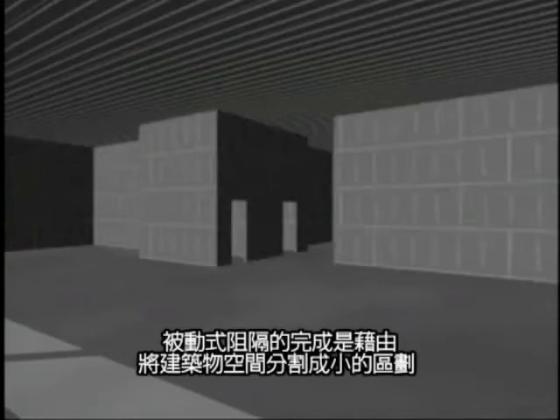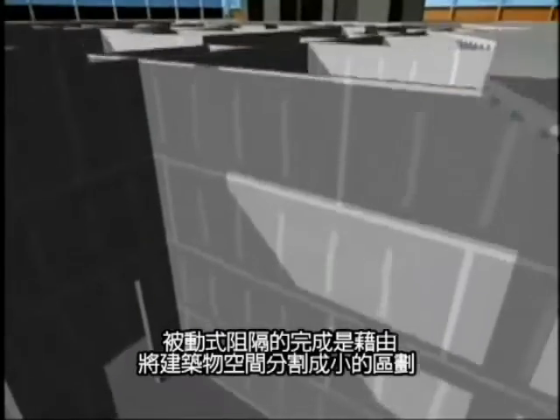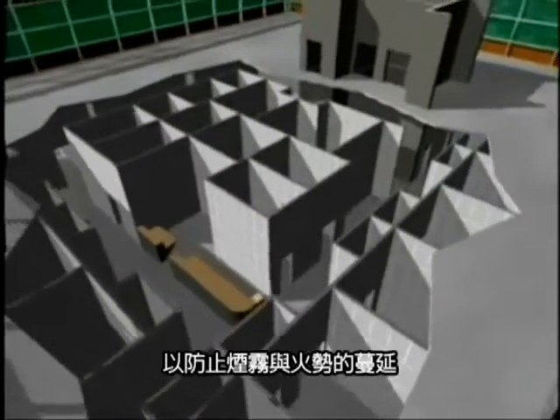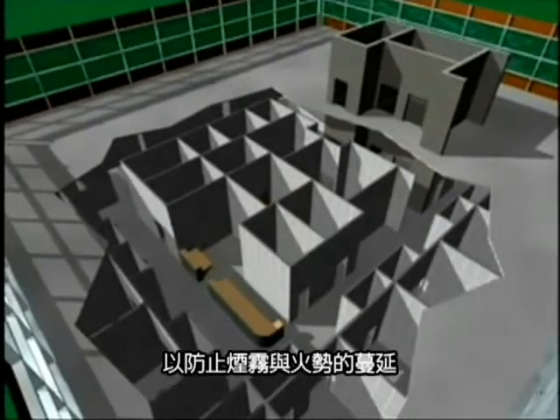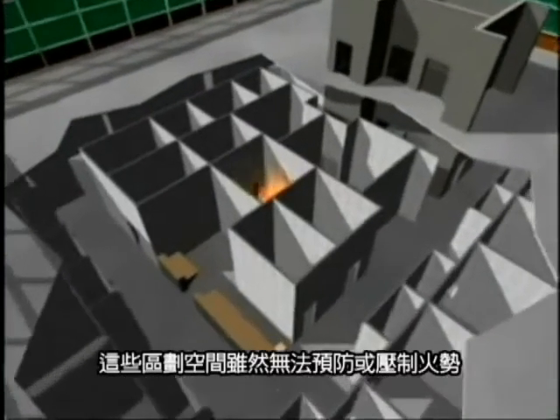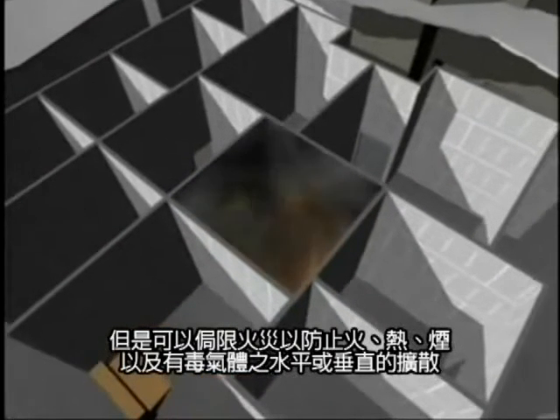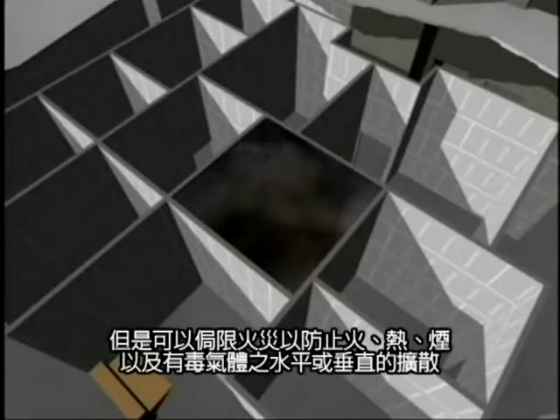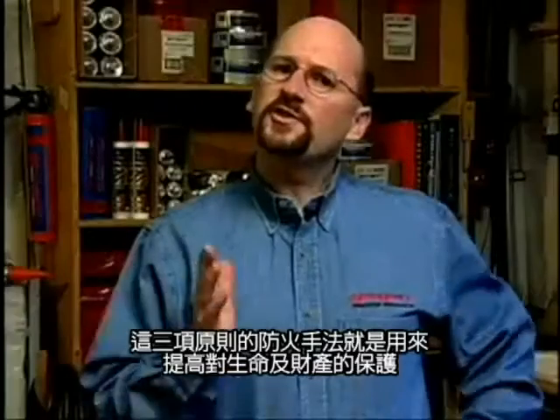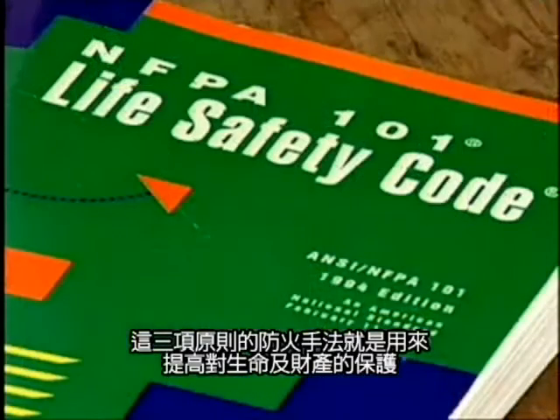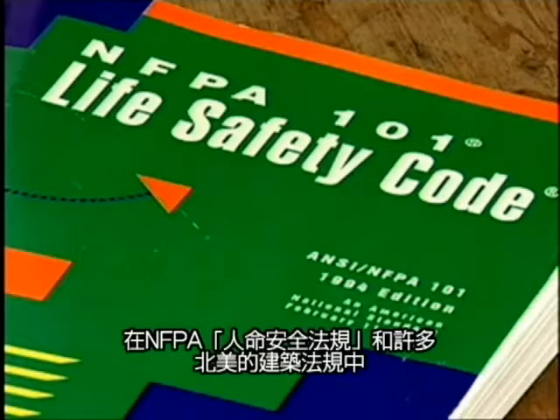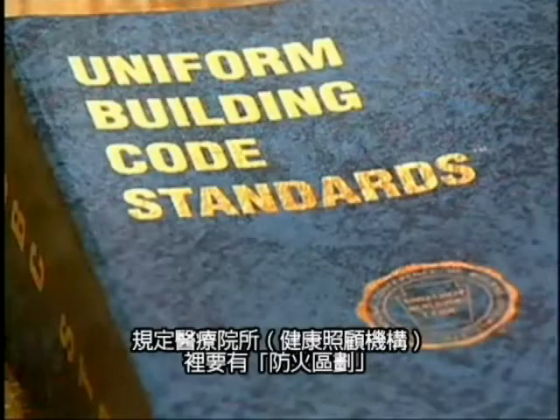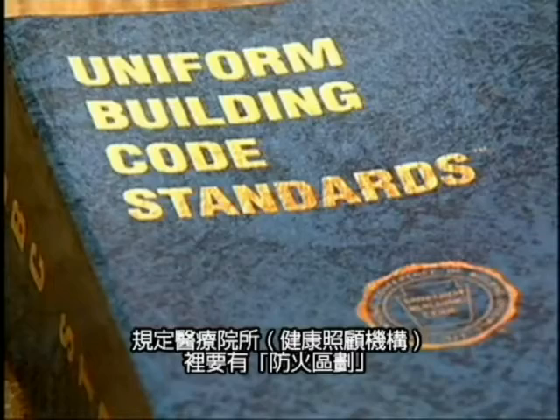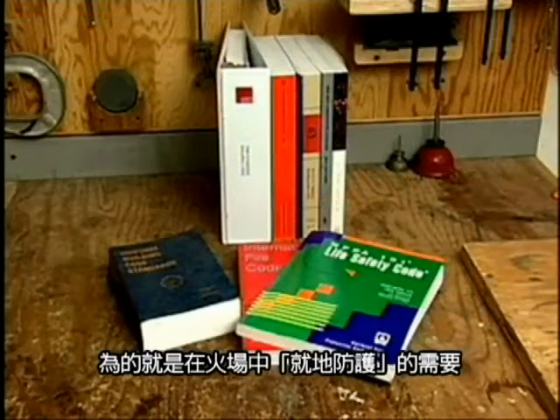Passive containment is accomplished by dividing building space into smaller compartments that are designed to minimize the spread of smoke and fire. These compartments will neither prevent nor suppress a fire, but will contain it to prevent horizontal or vertical spread of flames, heat, smoke, and toxic gases. This three-tier redundant approach to fire protection is designed to improve the odds for life safety and the protection of property. The NFPA Life Safety Code and all model building codes in North America mandate compartmentation in healthcare facilities due to the need for defending in place in a fire.